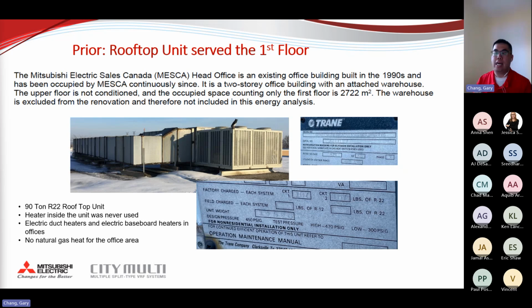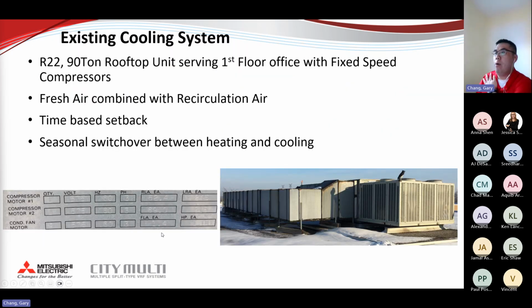And in the office area, there's actually no natural gas. So about 30-plus years ago, we were already utilizing electric for heating and cooling. So it was a 90-ton rooftop unit serving the first floor with fixed-speed compressors, and 10% opening on the damper to have fresh air combined with recirculation air, with time-based setback as well as seasonal switchover between heating and cooling. And you can see they are pretty old, pretty beat up from the outside, right? From the photos: 2 compressors and 4 condenser fans, at 575 volt, and able to do effective heating and cooling.